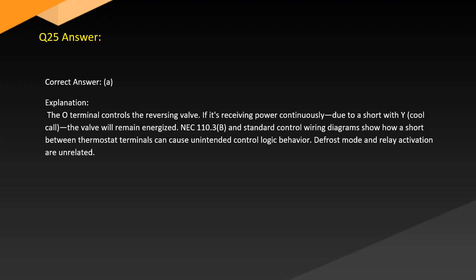Answer. Correct answer A. Explanation. The O terminal controls the reversing valve. If it's receiving power continuously due to a short with Y cool, the valve will remain energized. NEC 110.3(B) and standard control wiring diagrams show how a short between thermostat terminals can cause unintended control logic behavior. Defrost mode and relay activation are unrelated.